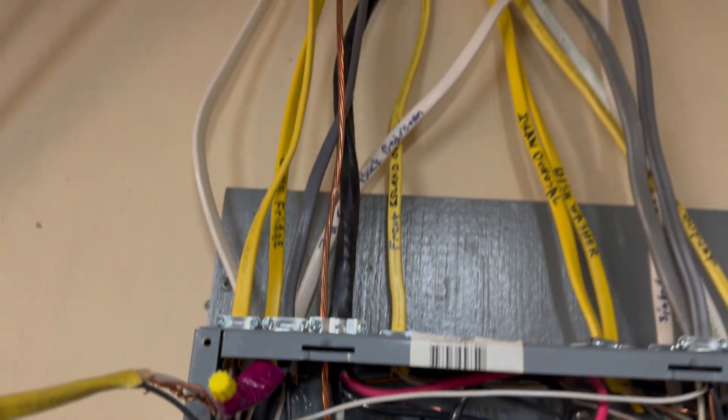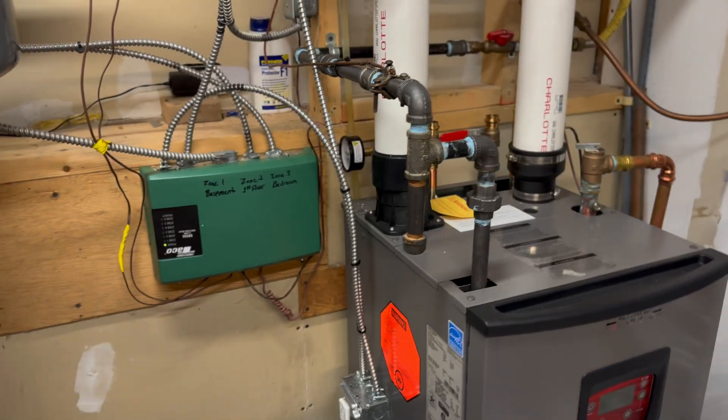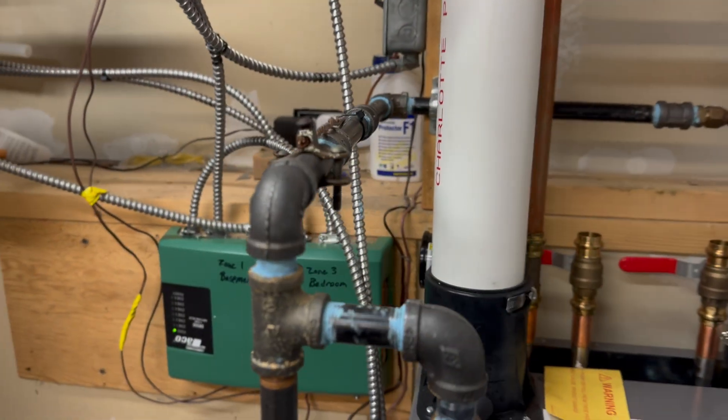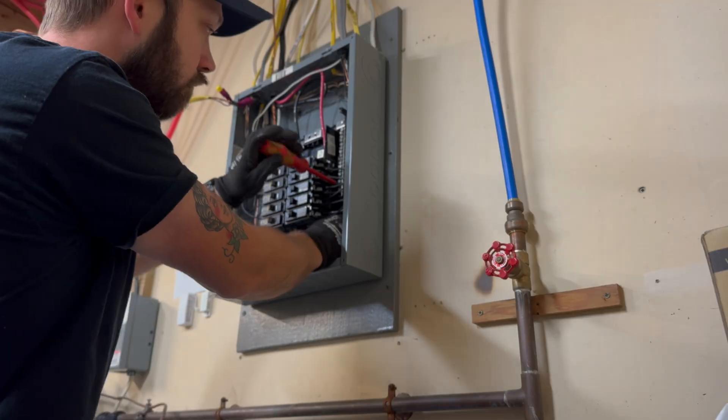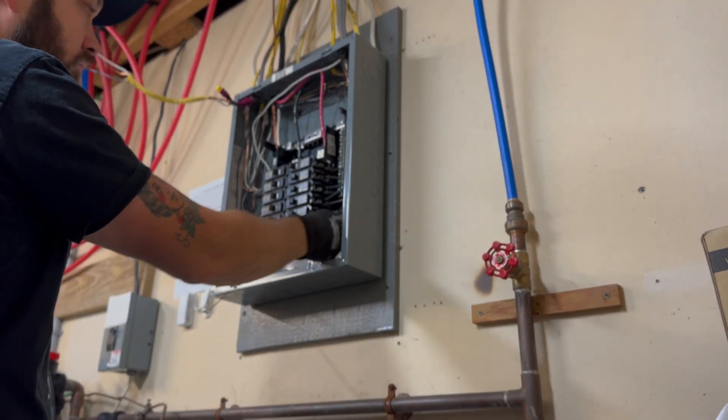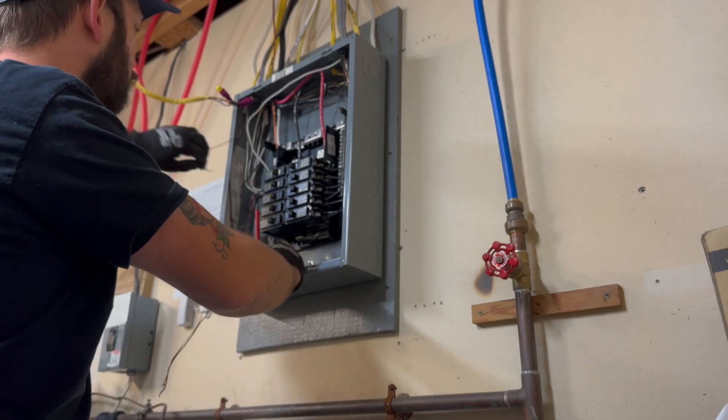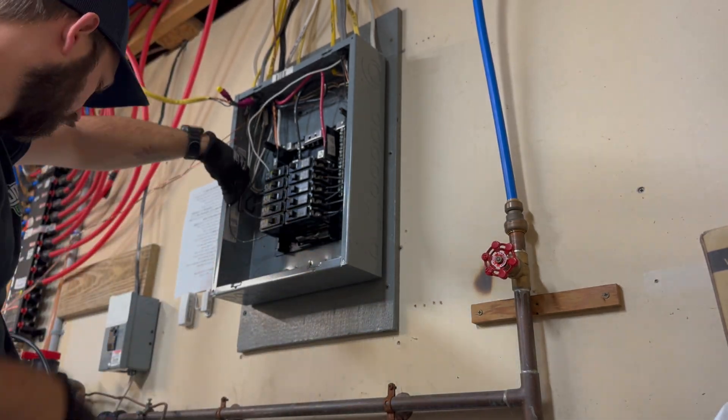And then here is a number six bare copper that's going over and bonding this gas furnace. Some CSST comes in and hits that furnace there, but that's just laying right on the neutral lug. Pretty big violation right there.